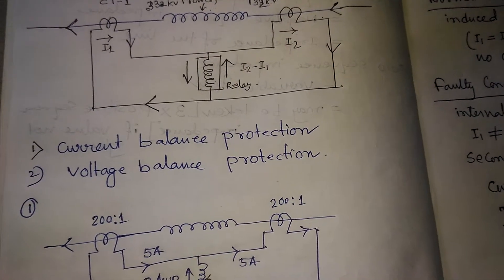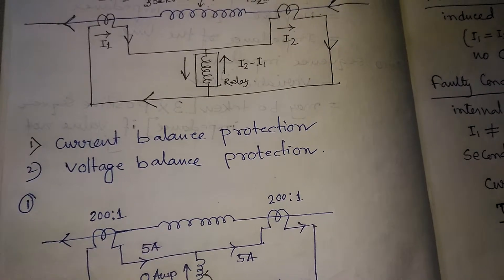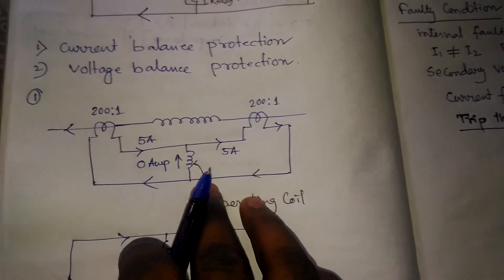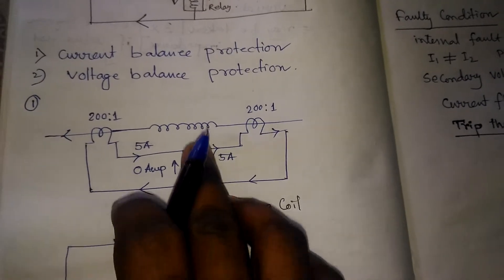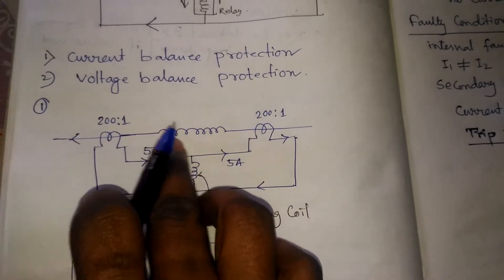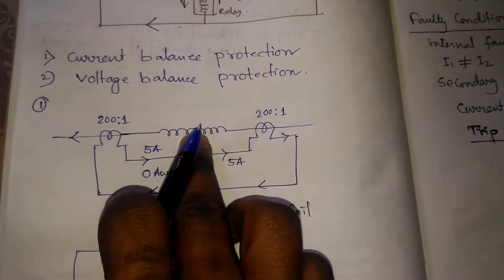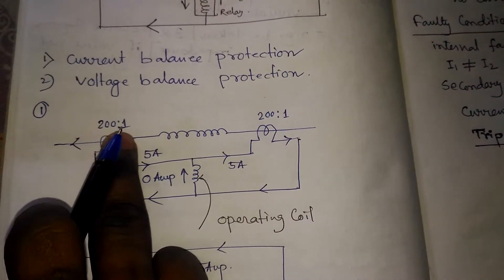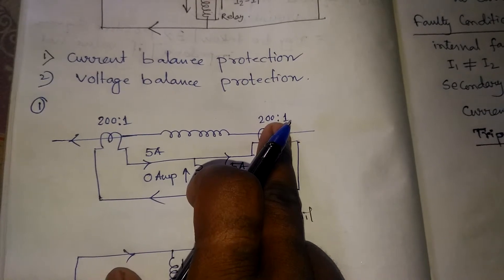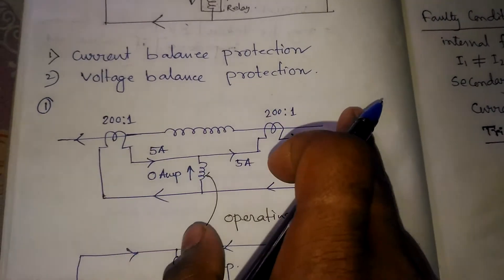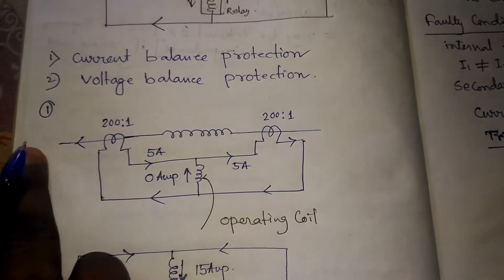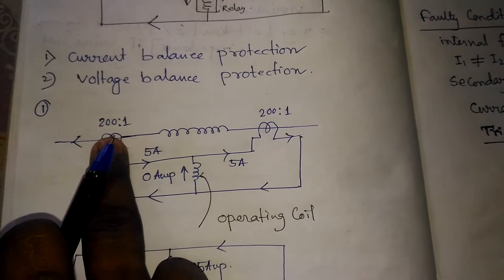Two types of protections are present: current balance protection and voltage balance protection. In the current balance protection scheme, it is for highly costly electrical equipment. We connect the CTs on both sides and the CT ratio is 200:1 on both sides. The current is flowing in a certain direction, suppose 5 amperes from CT1.